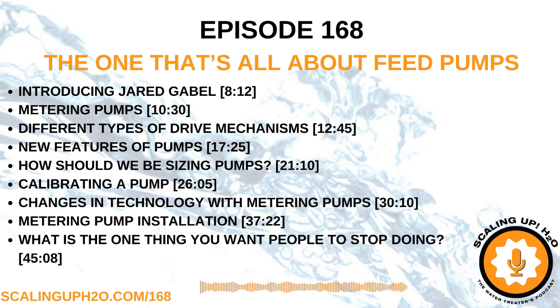One of the reasons I like this, as opposed to just applying power and turning it off, is that, like I said earlier, these metering pumps these days are smart. They've got computers built into them. So if you start cycling power on and off and on and off, that's not a good recipe for a product that you want to last a long time. So take advantage of the remote on-off type of scenario instead of powering it on and off. To me, that's an old school way of doing it when the pumps are much smarter now and able to use simple contact closures, a potential-free signal.